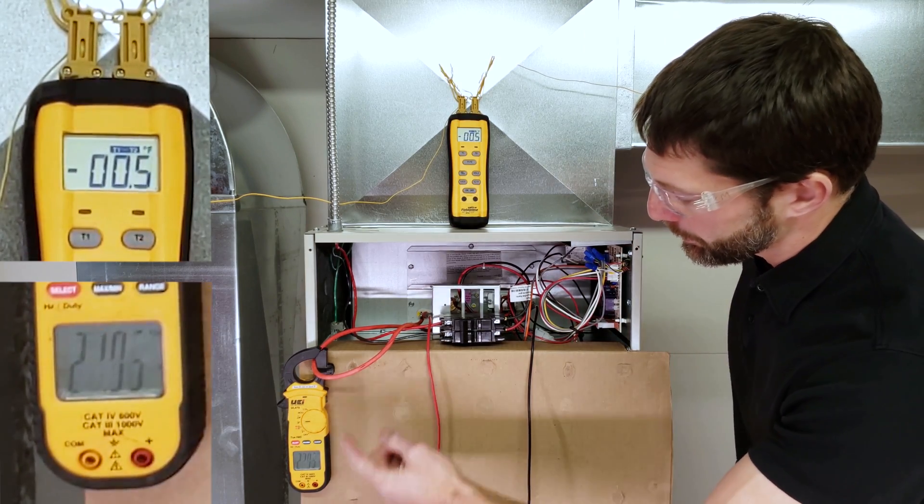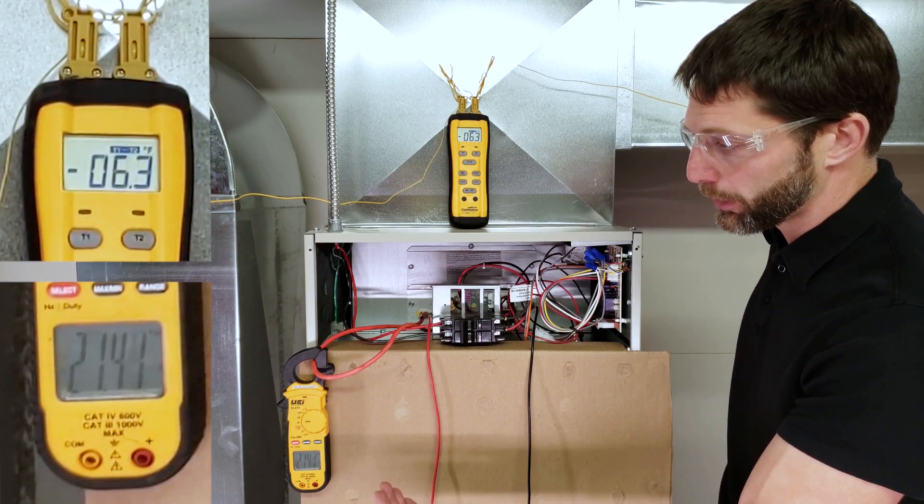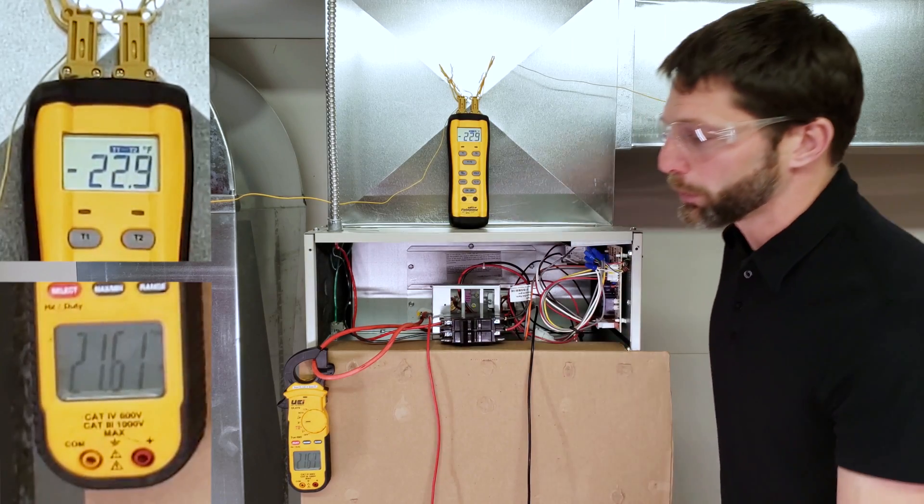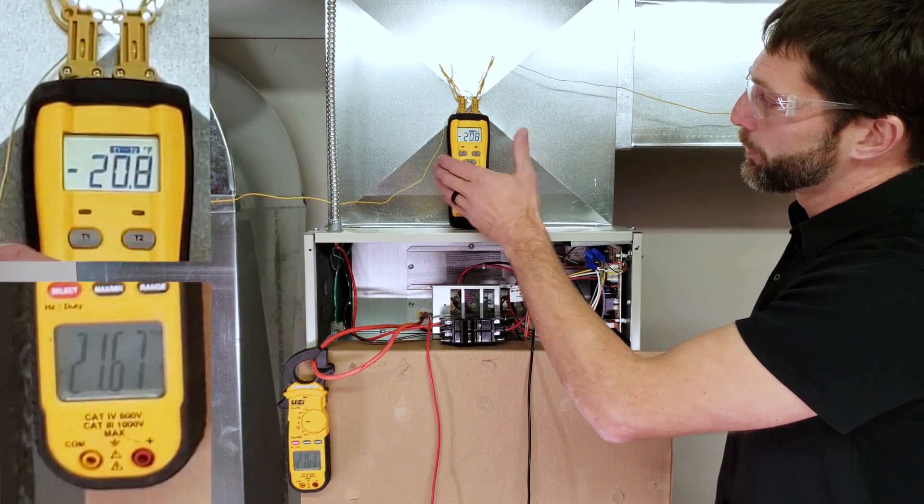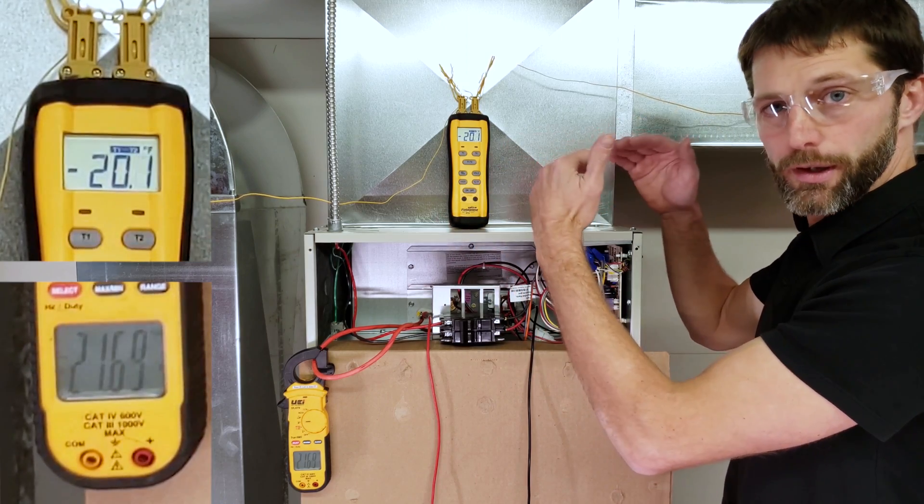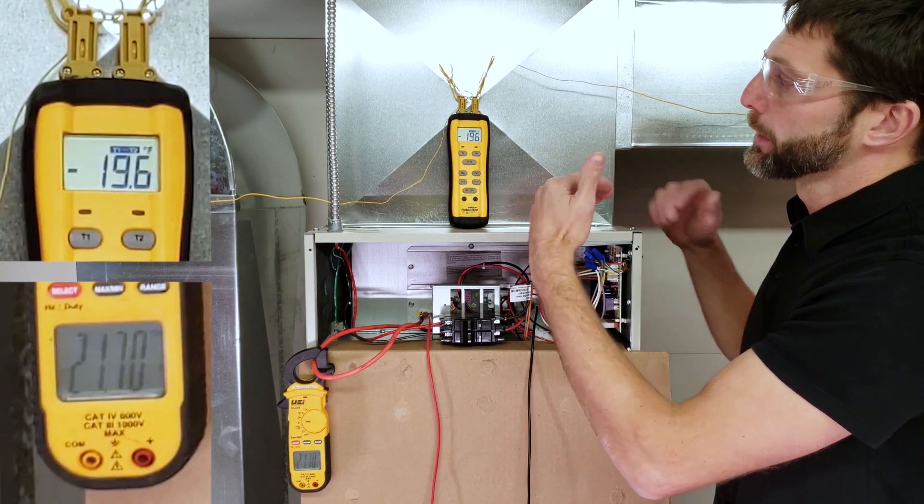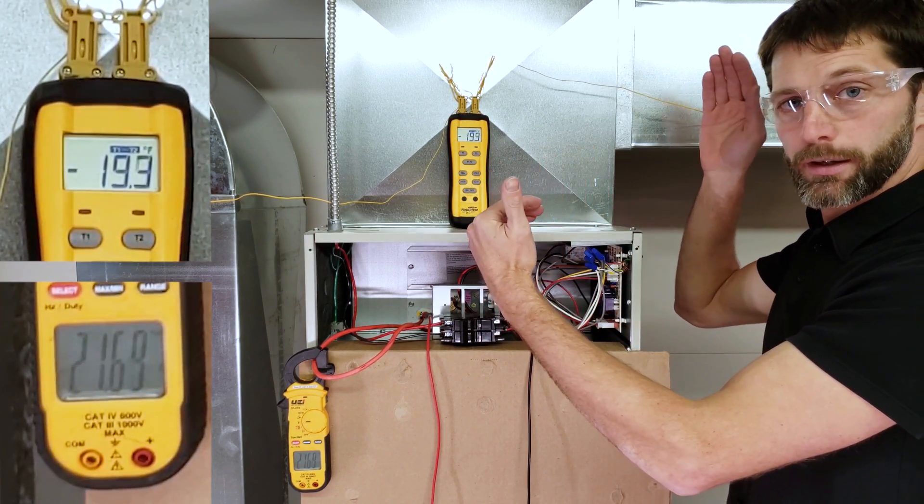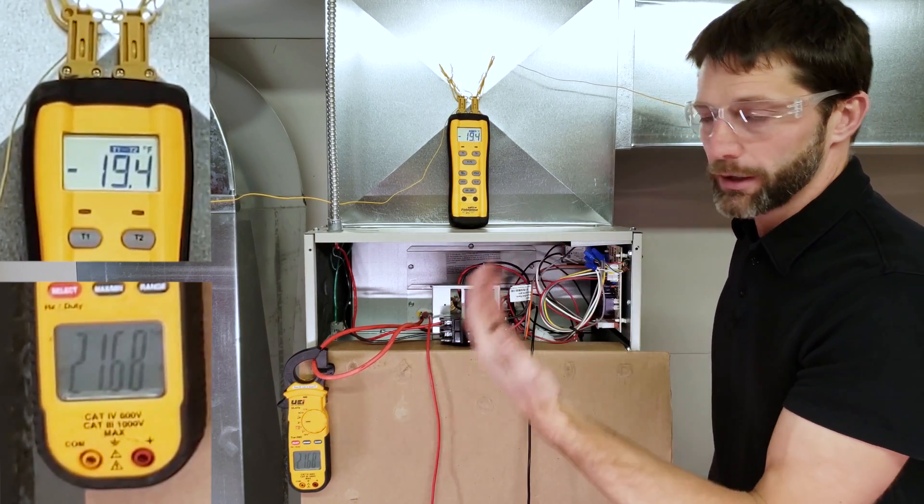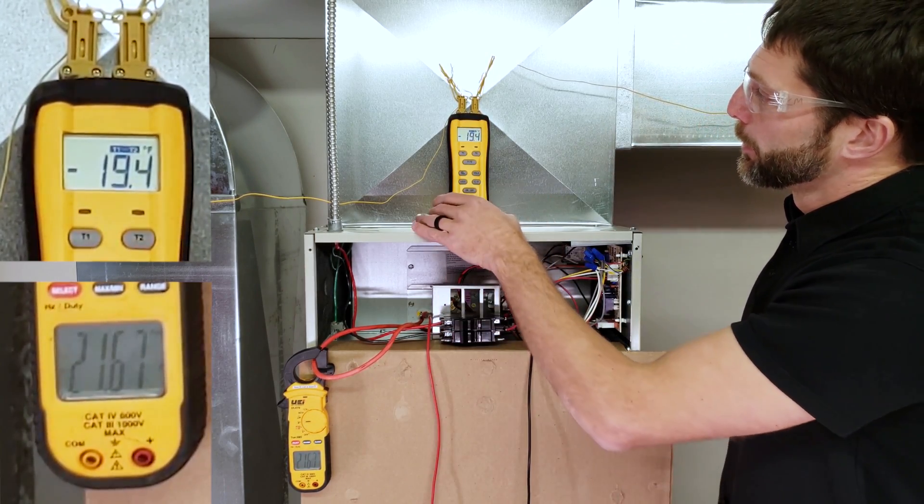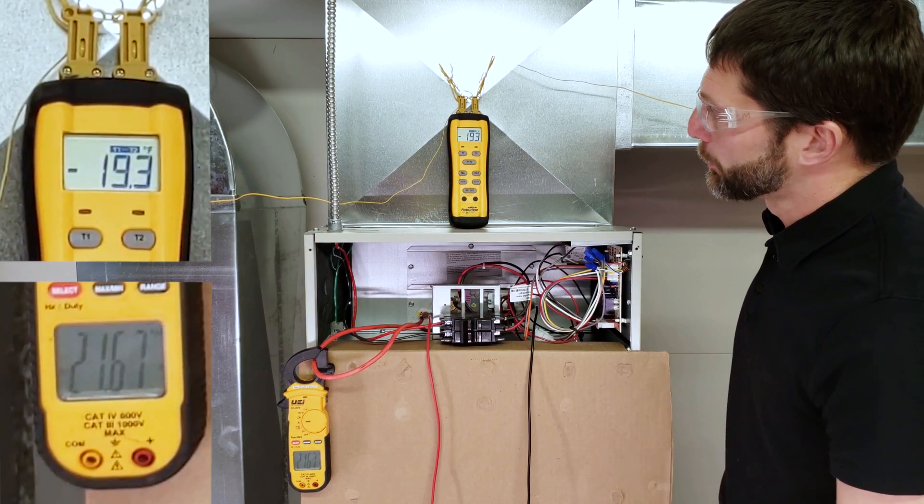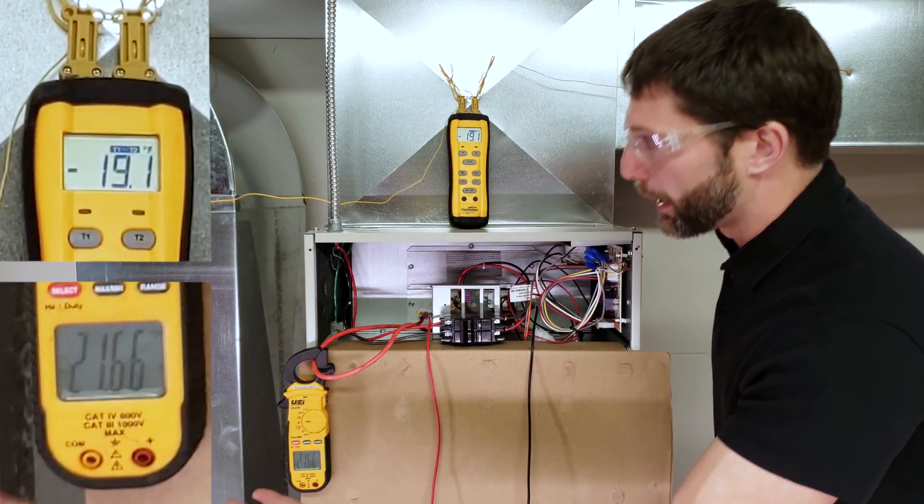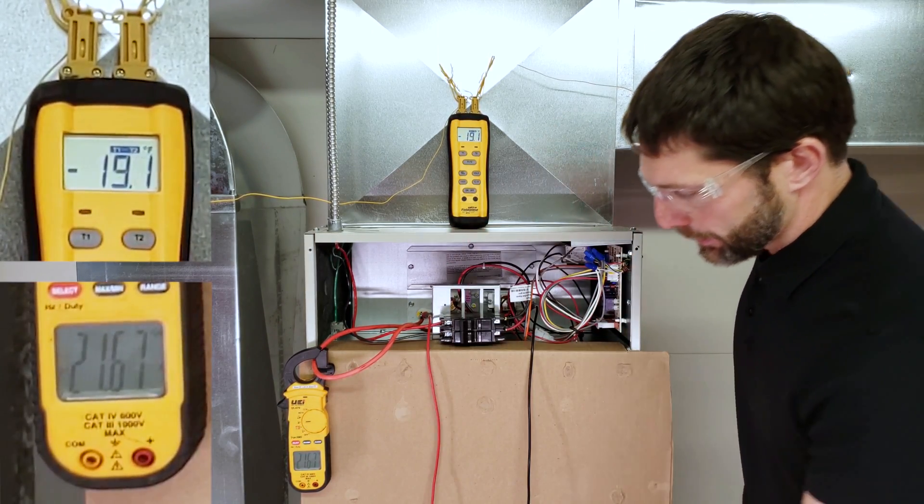The electric resistance is getting powered, then the blower motor turns on. Our amperage is right about 21.6 amps. We're looking for the temperature differential to settle into a constant. If it keeps rising, that means the blower motor speed isn't high enough or there's an airflow restriction. Right now we're reading about 19.3 degrees as a temperature differential and 21.65 amps. Let's check our voltage.